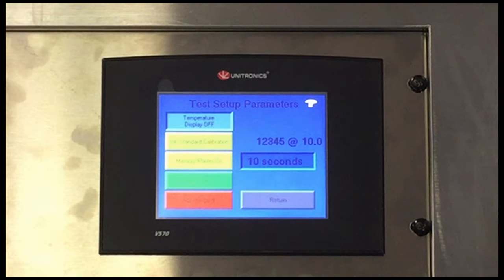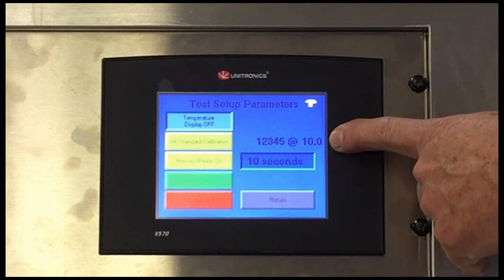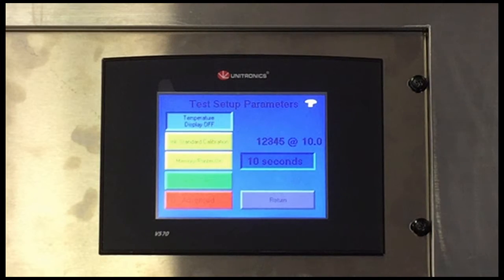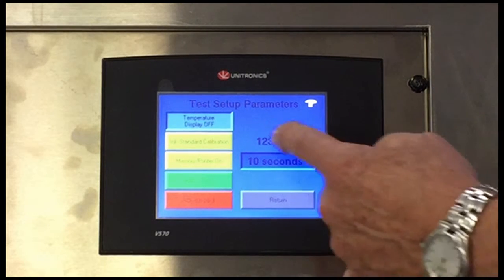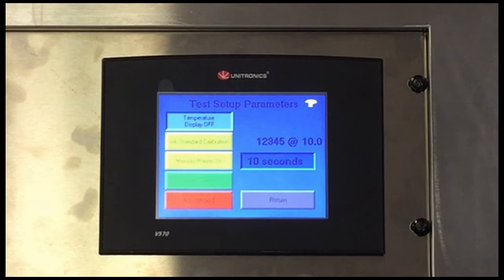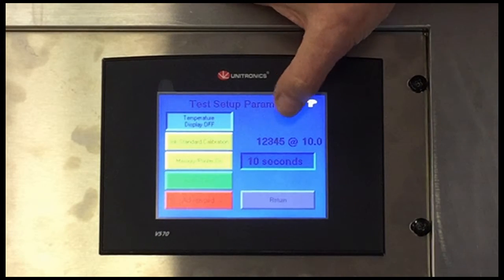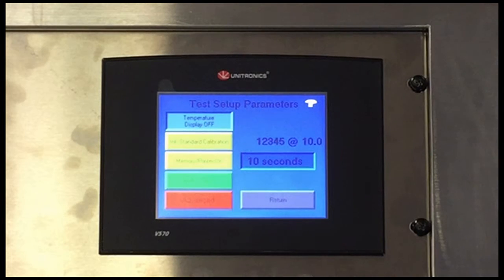For example, if you were to hand me an ink and it had a lot number of 1122 and you wanted to use that as your calibration standard, when we go through the calibration, which we're going to do in a little while, there's a section there where I can key in that 1122, and the number over here, that's the actual tack standard that we adjusted it to. So if there's ever a question as to what ink standard was used for the calibration and what the ink standard number was, that information essentially is generated right here on this line. You'll get a better understanding of this when we actually go through the calibrations.